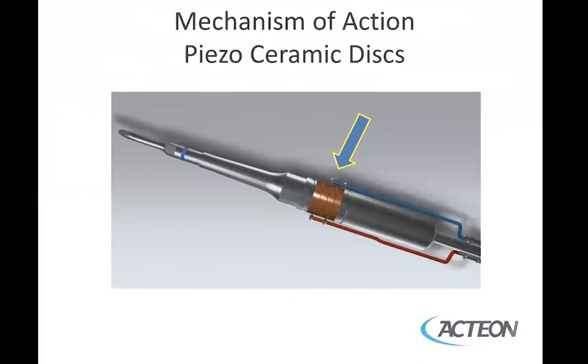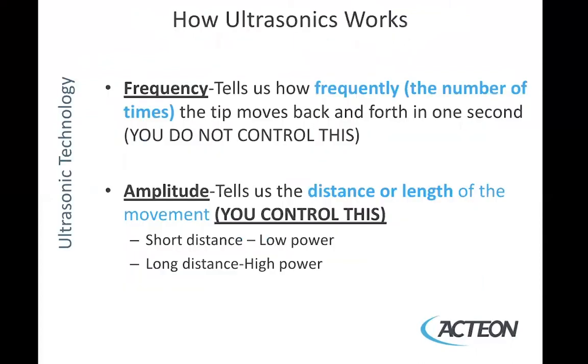The mechanism of action involves the piezo ceramic discs in the handpiece. The electrical current excites the four discs and the energy travels through the handpiece, creating a linear motion of the tip.